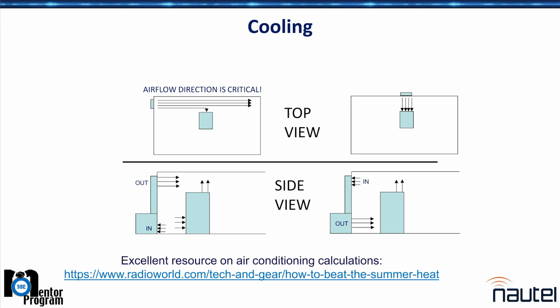The top one is looking at forced air, and like I said, I've walked into more sites where the air's being blown past the back of the transmitter at a couple hundred kilometers an hour, creating a negative pressure zone with almost no air going through the transmitter. Direct the air through the transmitter.